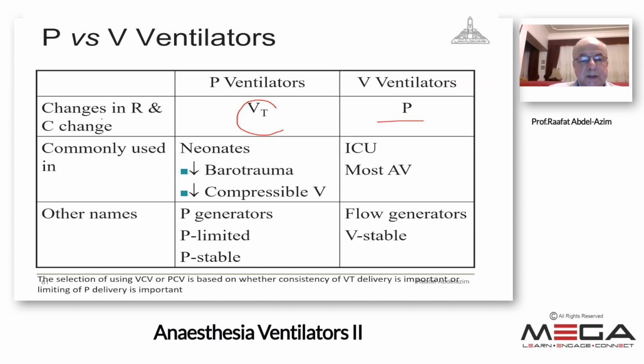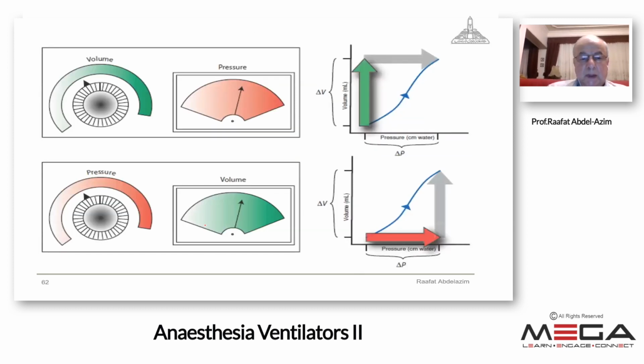If there is any change in resistance or compliance, I will explain later, there will be change in the other parameter. So for volume ventilators, I adjust the volume, but any change in resistance and compliance will affect the pressure, and the reverse in the pressure ventilators. Volume ventilators are commonly used in most of the anesthesia ventilators and in ICU. Pressure ventilators are used also in anesthesia, but for neonates, and I'll explain later. Here, the volume ventilators in the top view are this one. I adjust the volume and I measure the pressure, and in pressure ventilation, I adjust the pressure and measure the volume.